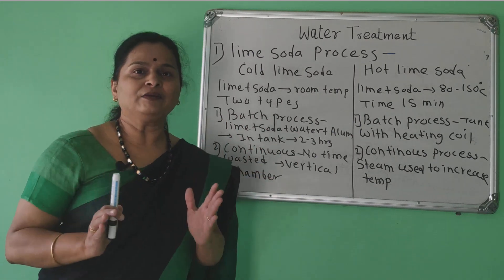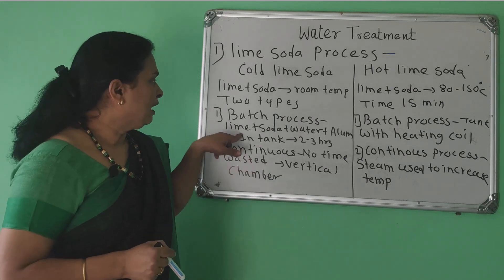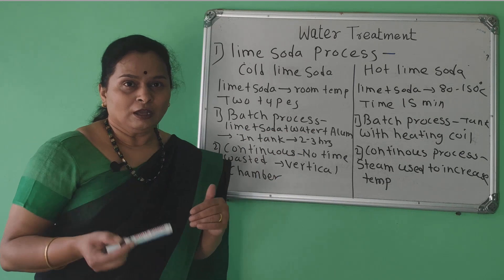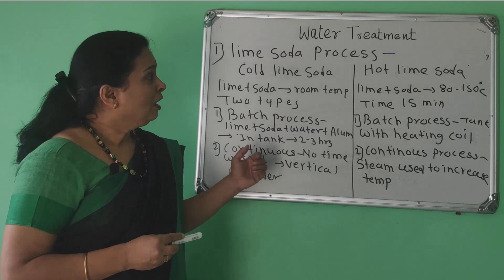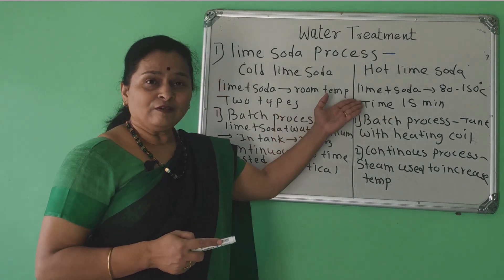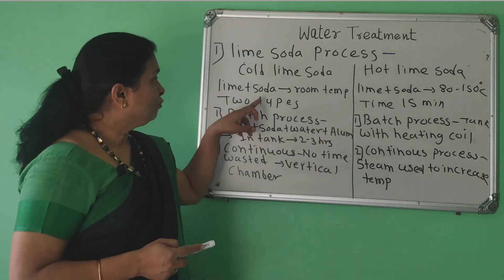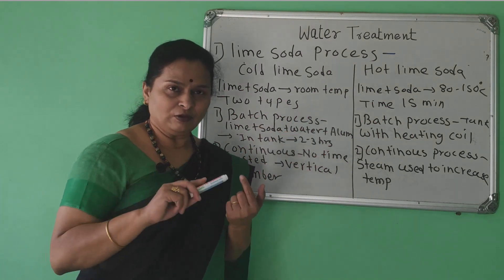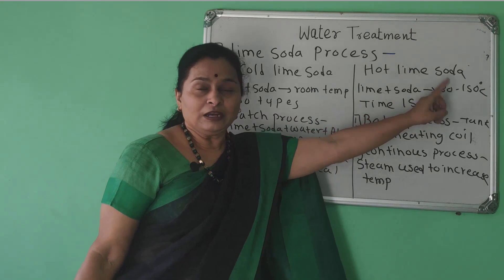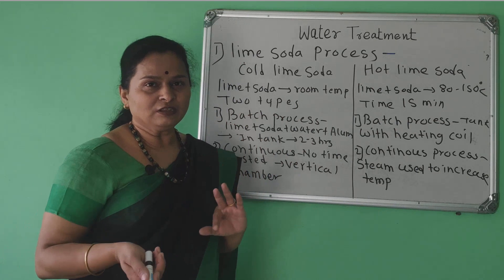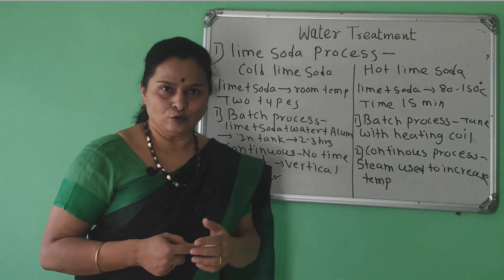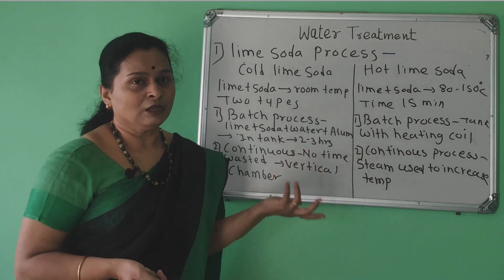In the continuous process, a cylindrical vessel is used. Lime, soda, water, and alum are added from one side, and soft water is obtained from the other side. No time is wasted in the continuous process. In the hot lime soda process, lime water is added to hard water at 80 to 150 degrees Celsius. The time required for the hot lime soda process is 15 minutes, compared to 2 to 3 hours for cold lime soda. In the batch process a tank with heating coils is used to raise temperature to 80–150°C, while in the continuous process steam is used to increase the water temperature.